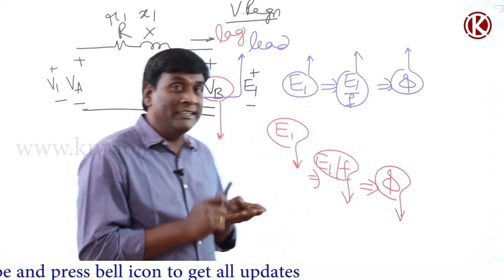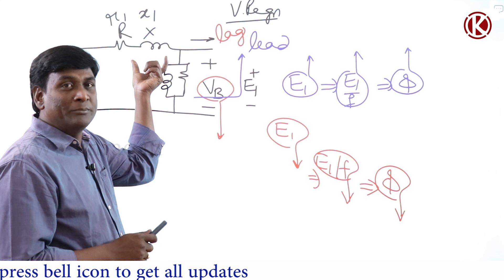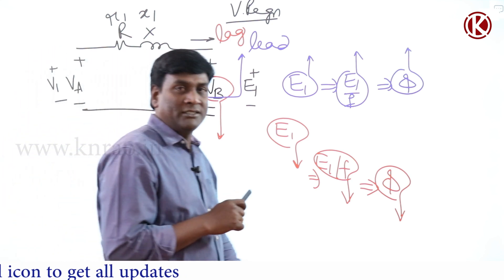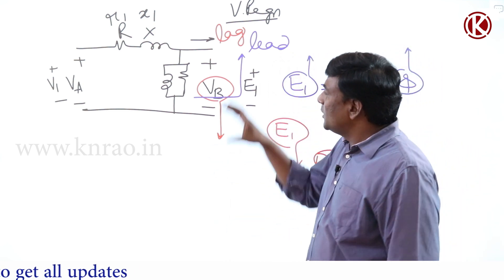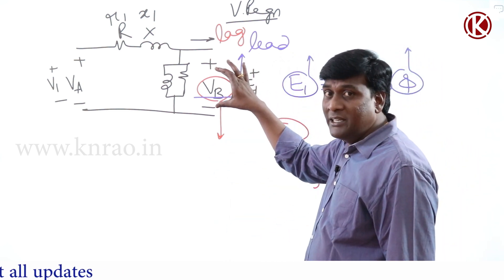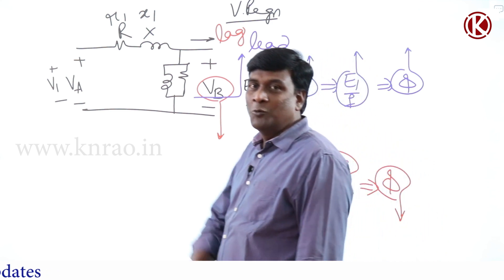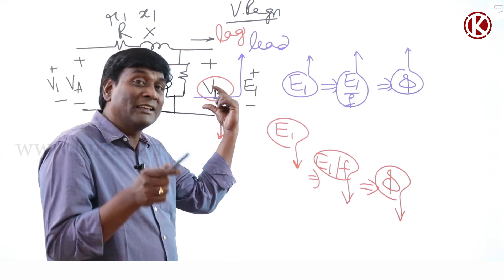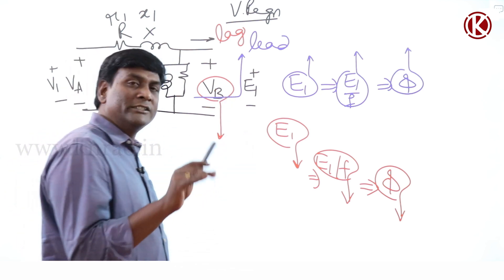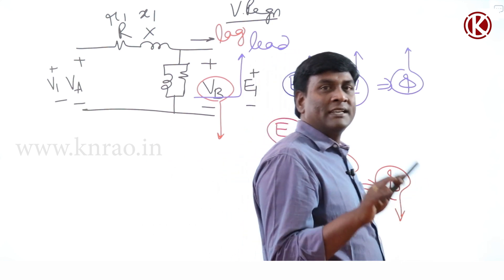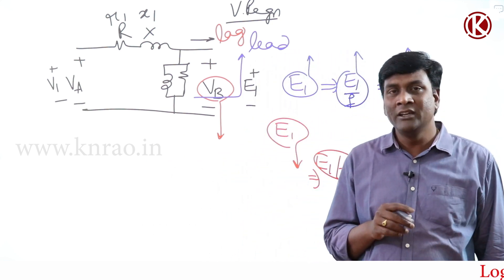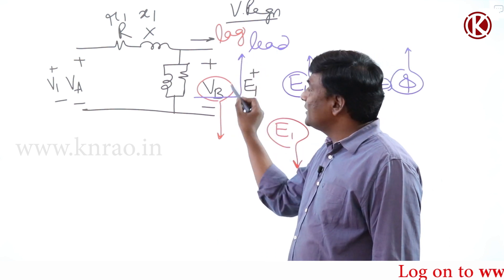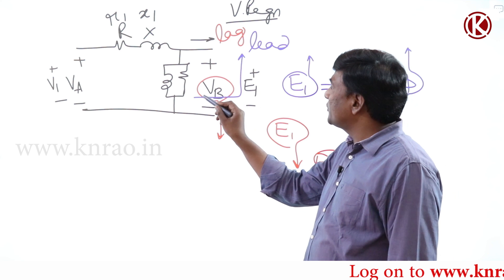But this variation is going to be much less. Because of the lack of air gap, leakage flux is least, leakage reactance is least, leakage impedance is least. So the voltage drop across leakage impedance is least, meaning voltage variations across the shunt branch are least. We may consider — I repeat, we may consider — those voltage variations are not happening by neglecting them. Only under that condition can I say the transformer has constant flux.